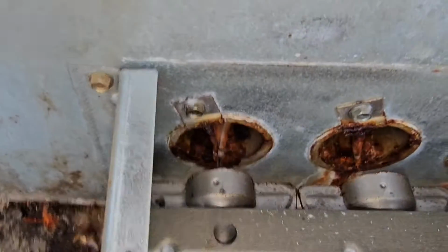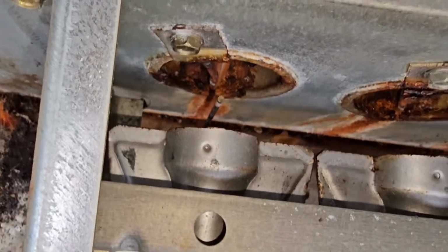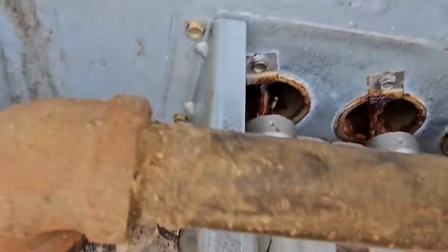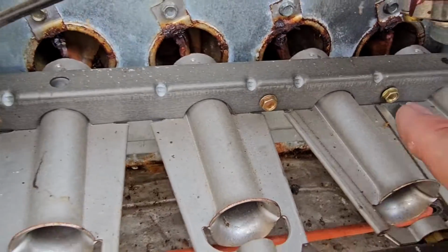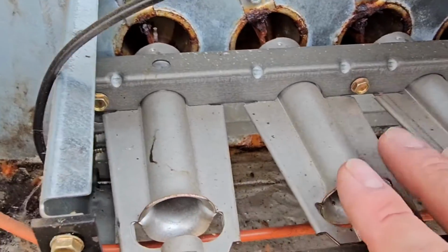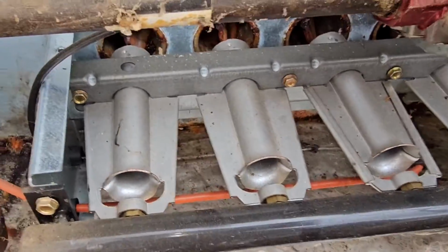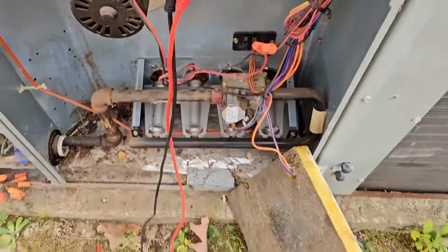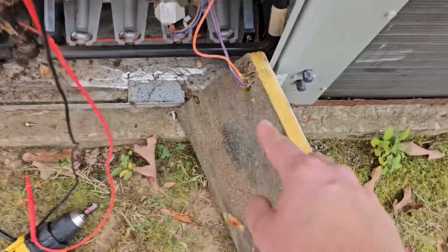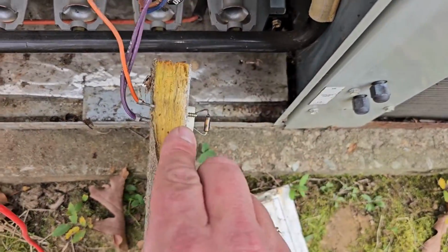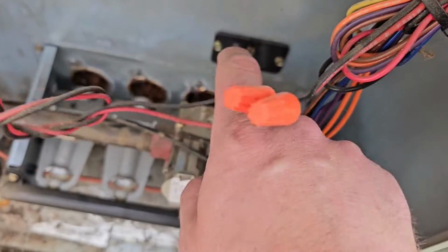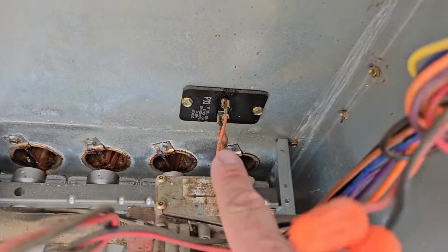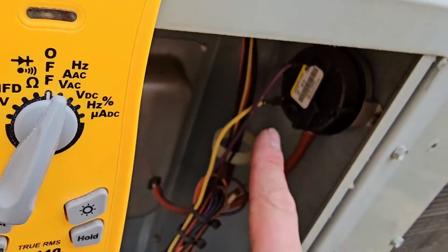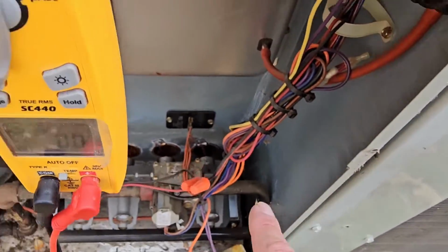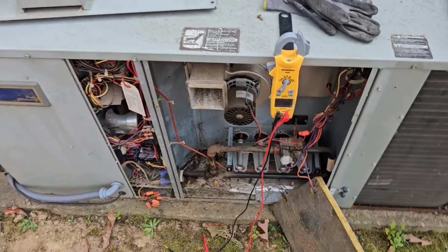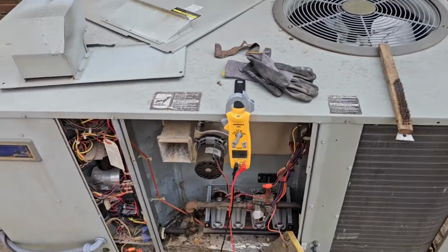That's dirty. We need to get some sandpaper or some type of cloth to clean that. And then we'll take these 3 screws that hold the burners in place. We'll take those out and then take the burners out. We keep burners in stock. We keep rollout switches like this in stock. We keep those limit switches in stock. We keep pressure switches in stock. And that's what we keep in stock for this particular American Standard package unit.